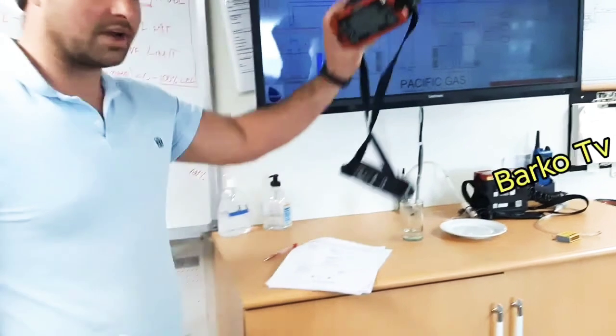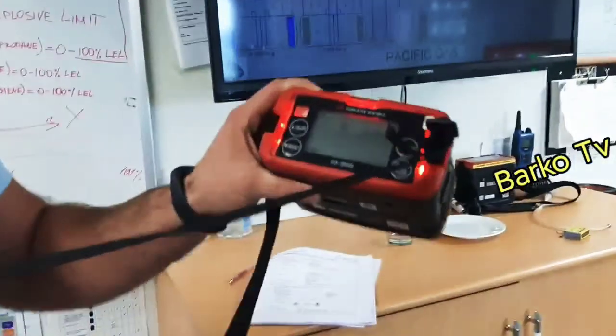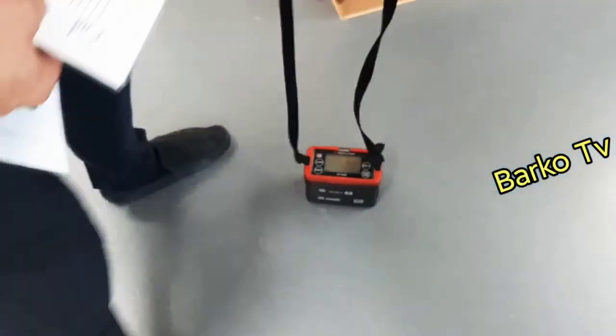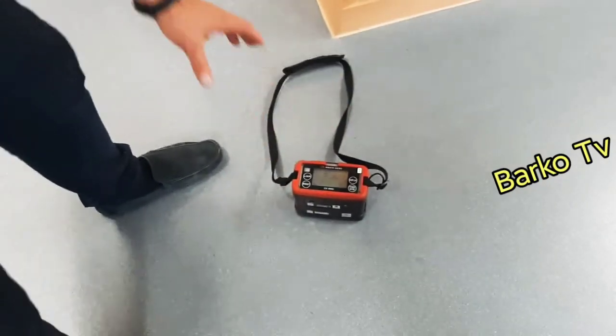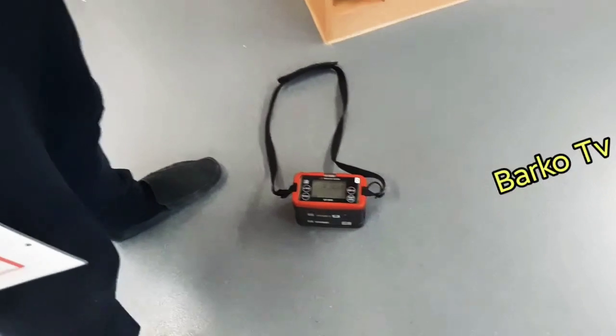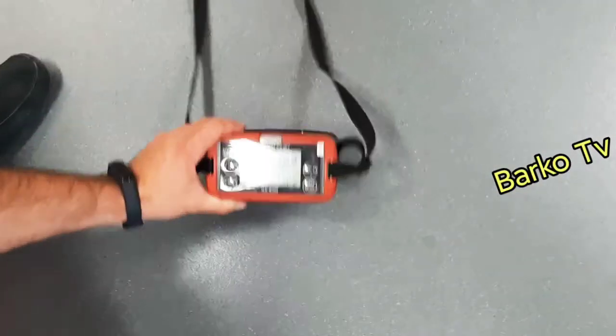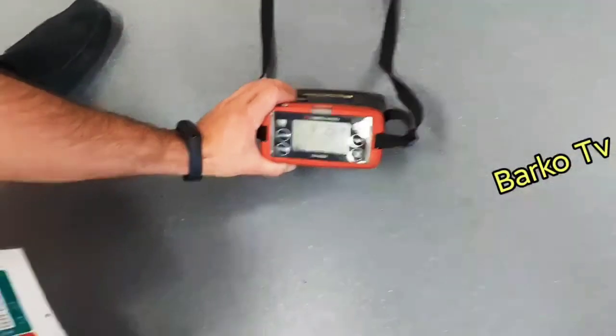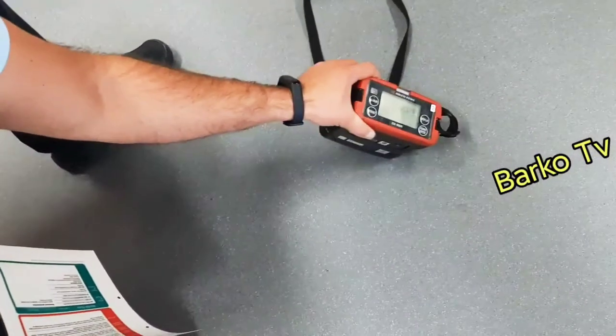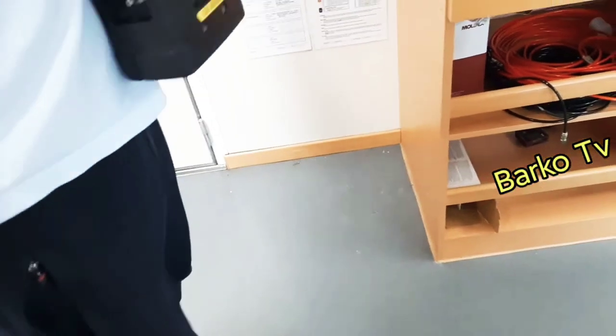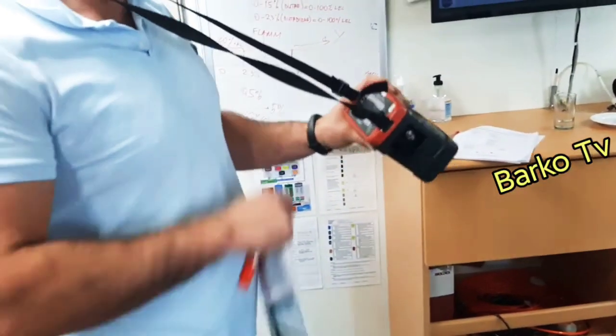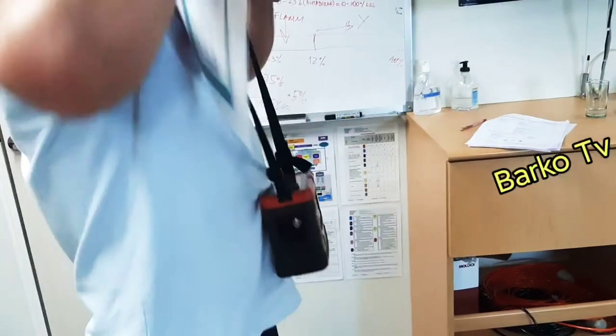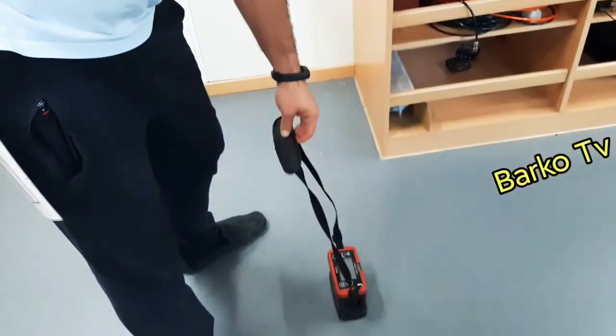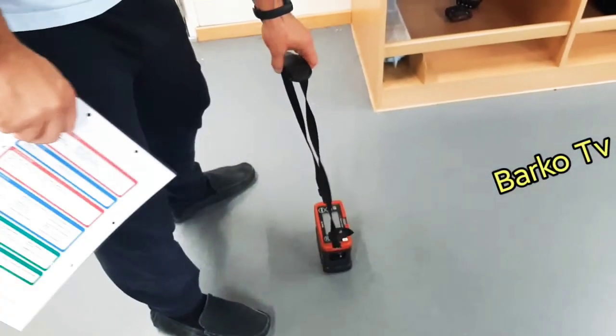Just remember, when you are using the detector, that's a very important thing. When you are checking the atmosphere, you have to hold it vertically, stick on the floor. If you hold it like this, it will not give you a correct reading. It will give you a wrong reading. That's why when you are measuring, you have to put it on the surface.